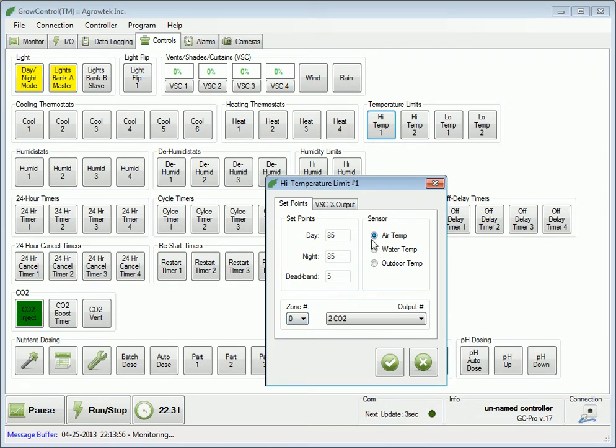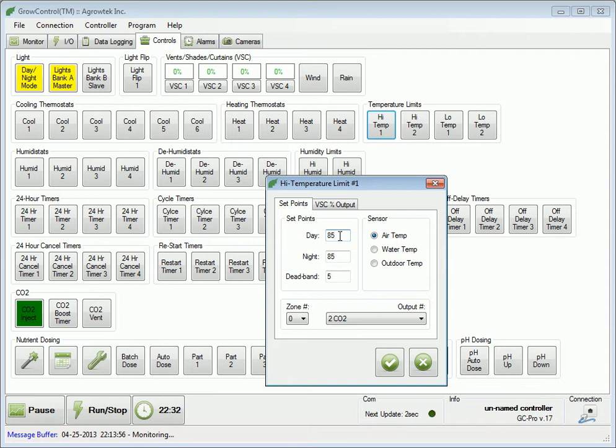In our application here, when the temperature rises above 85 degrees, the limit thermostat will be activated. CO2 will be disabled until the temperature falls by 5 degrees.